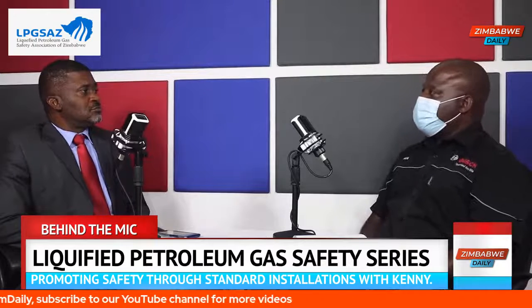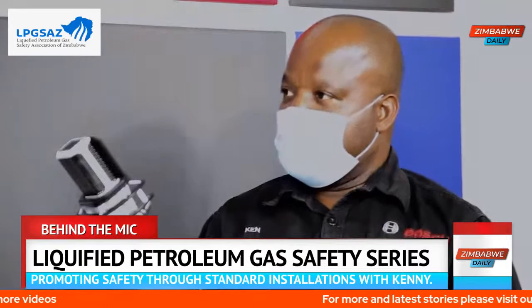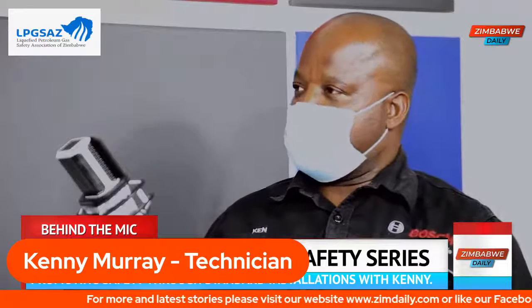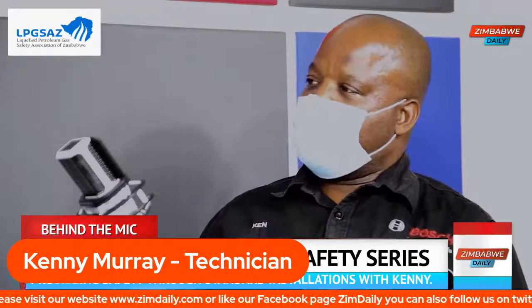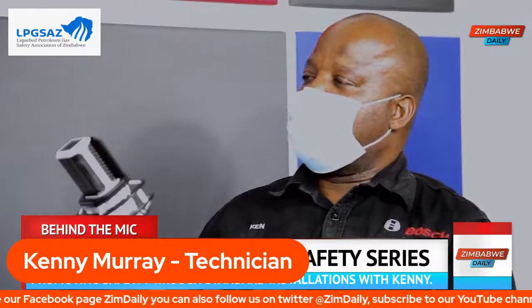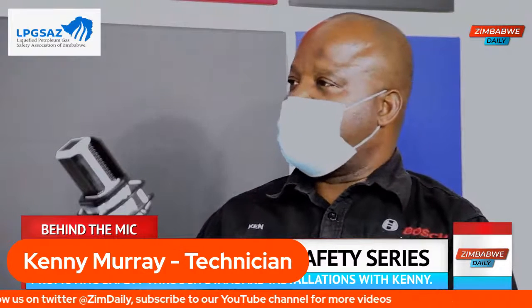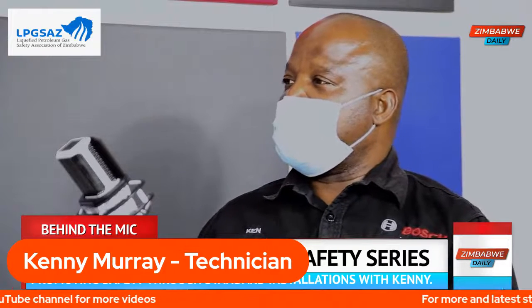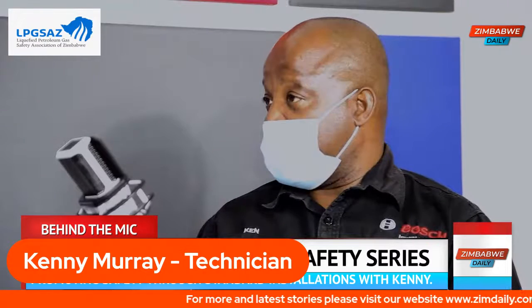Now, the scenarios we've had are not so much about natural gas because we are not using it yet. The main issue is that the jets which are used on certain appliances for natural gas are bigger than LPG. So if you use LPG on these natural gas appliances, the flame is much bigger because there's a free flow into that jet. Some people have hurt themselves or their pots have been burnt because the heat that's coming out of there is much more than a controlled flame from an LPG jet.